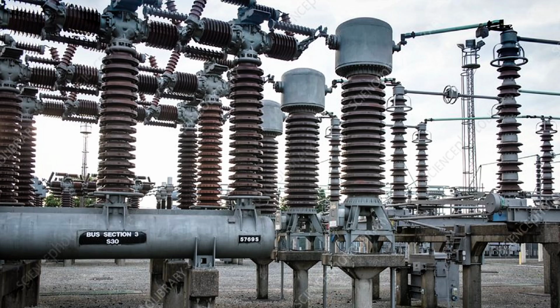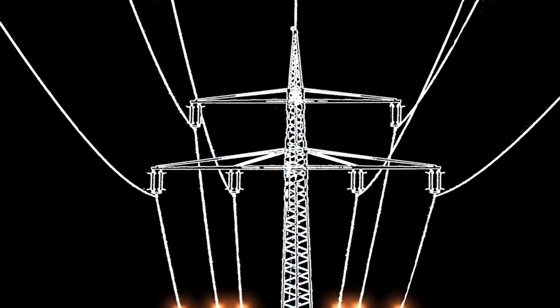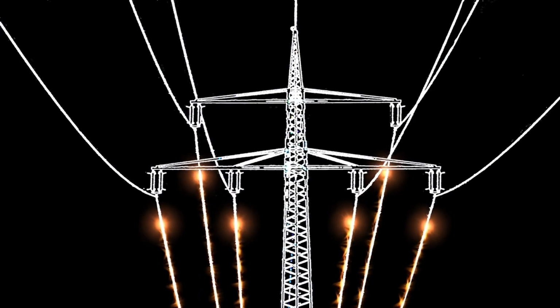One of the key benefits of the cross-blast type is its ability to provide effective arc extinction. This effective arc extinction reduces the risk of damage to the circuit breaker and other equipment, minimizing downtime and maintenance costs. Because it can be used in a variety of applications, including those where the arc path is complex or unpredictable, the cross-blast type is a popular choice for many users. Its ability to provide effective arc extinction in a wide range of applications makes it a reliable and versatile design. So, this is all about the cross-blast type circuit breakers.